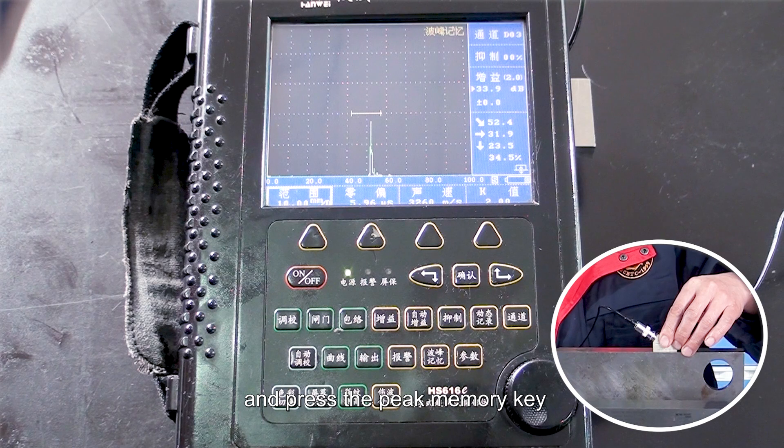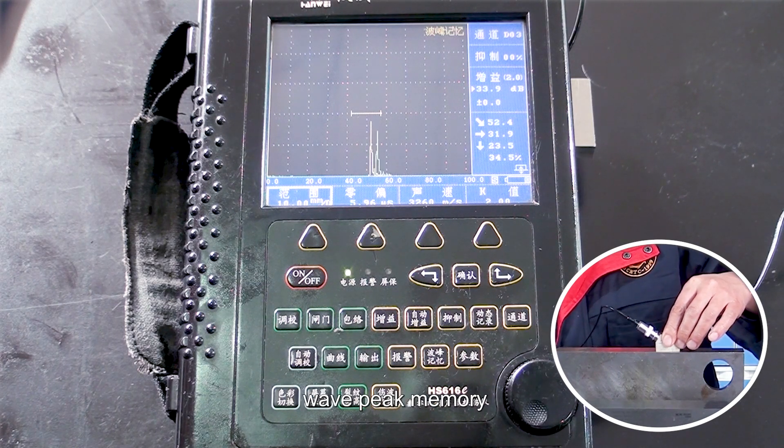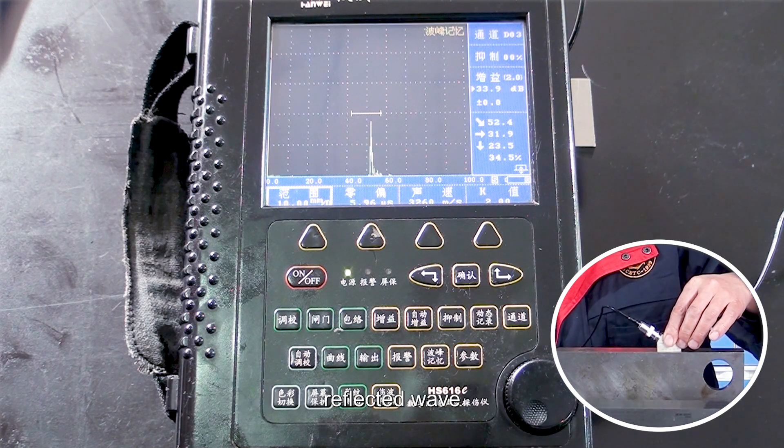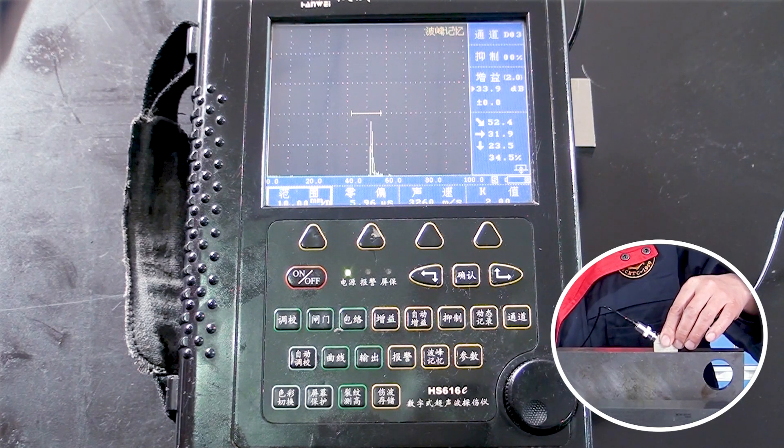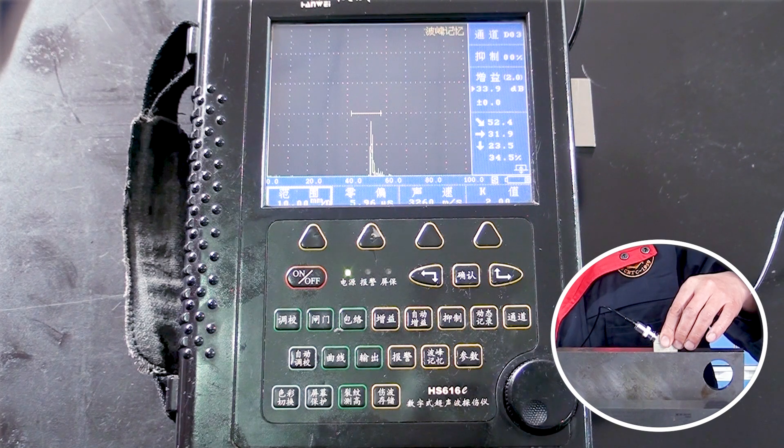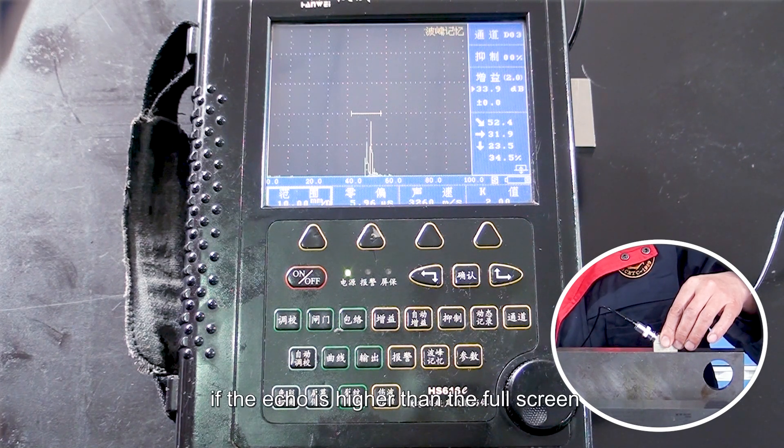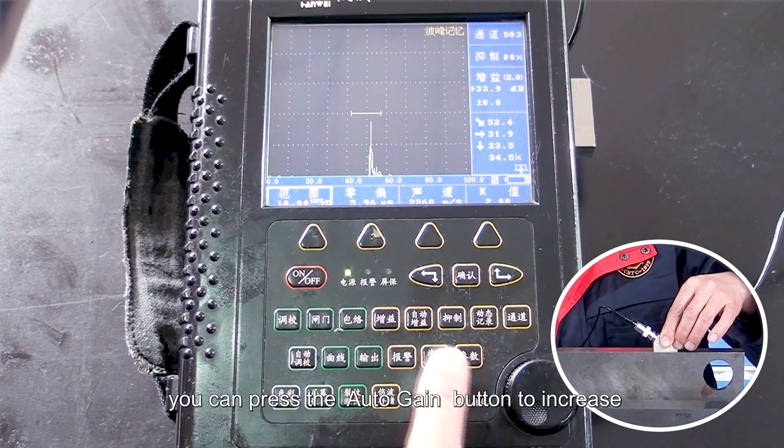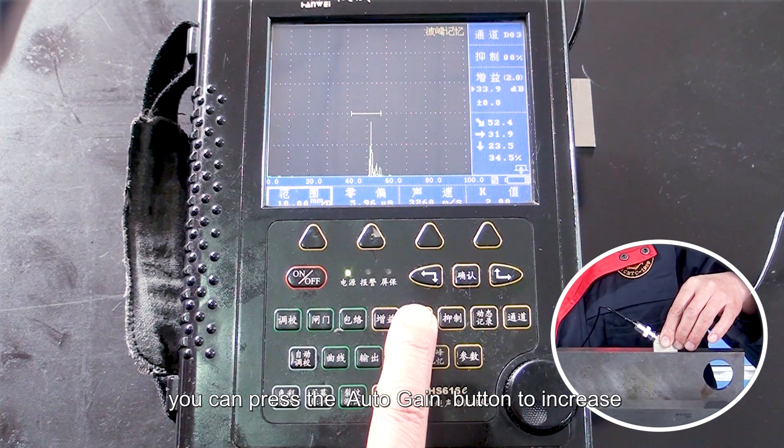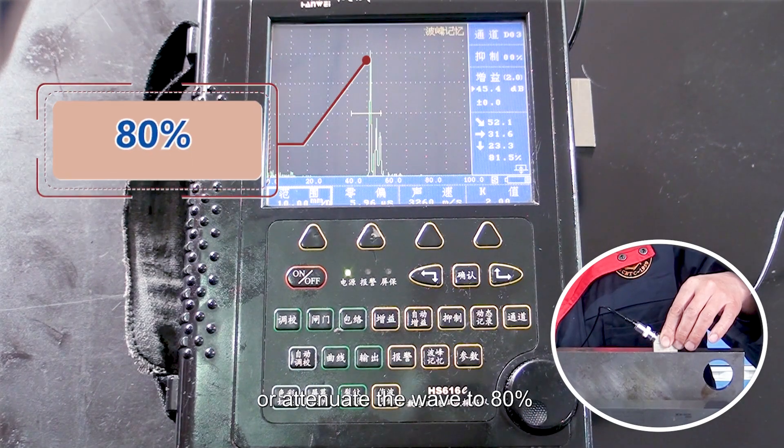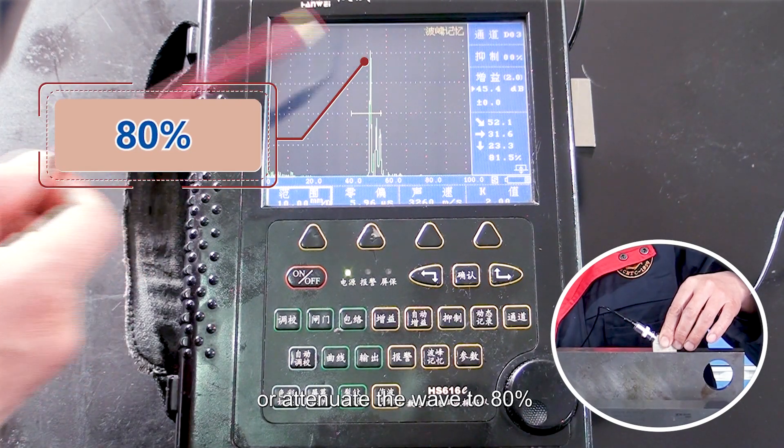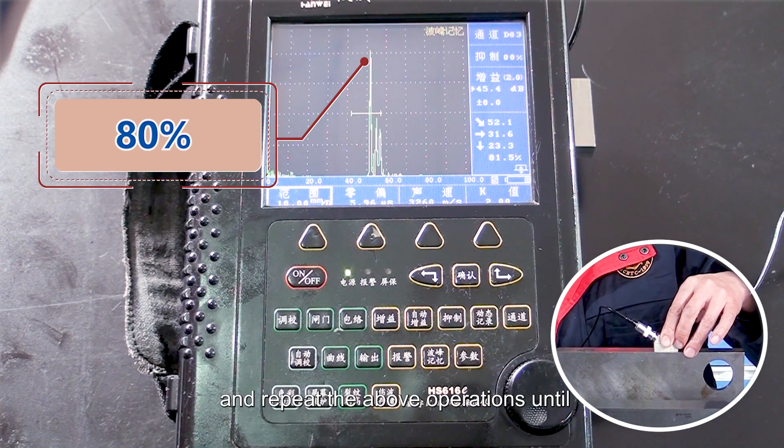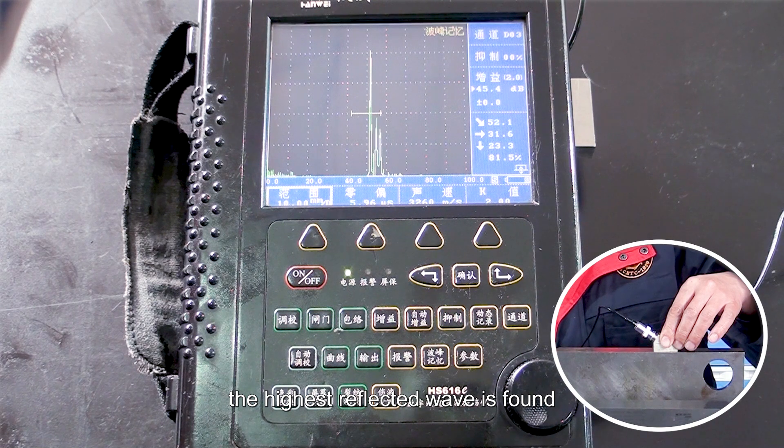Cover the reflected wave of the hole with the gate, and press the peak memory key to move the probe back and forth to find out the highest reflected wave of the hole. At this time, if the echo is higher than the full screen or lower than 20 percent, you can press the auto-gain button to increase or attenuate the wave to 80 percent, and repeat the above operations until the highest reflected wave is found.